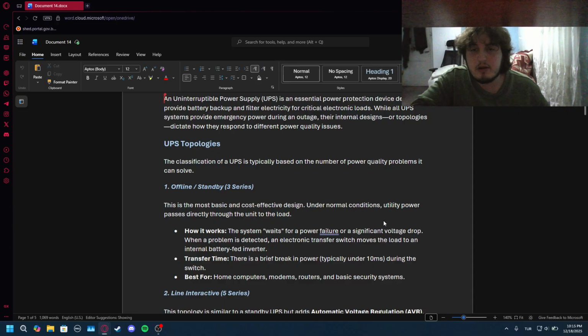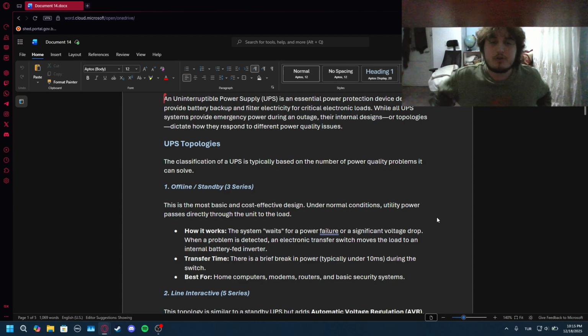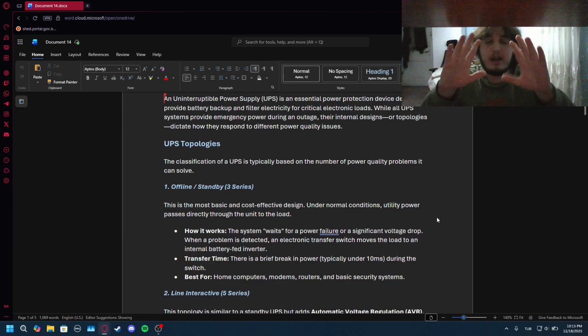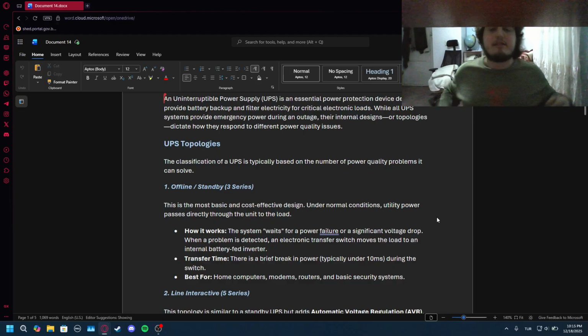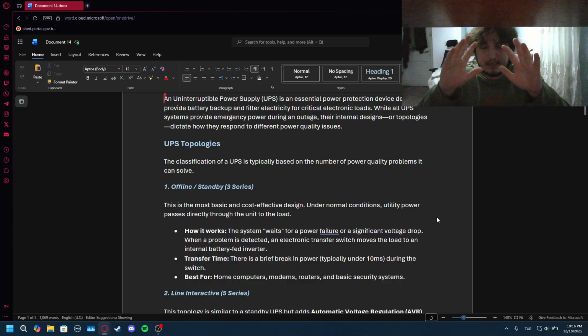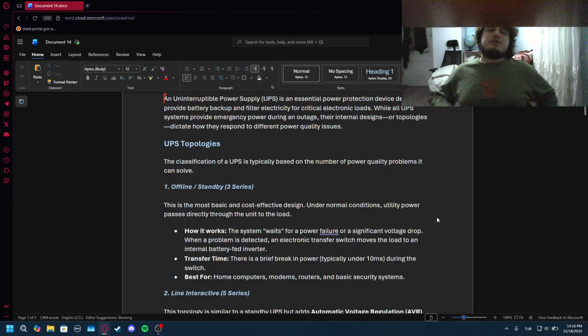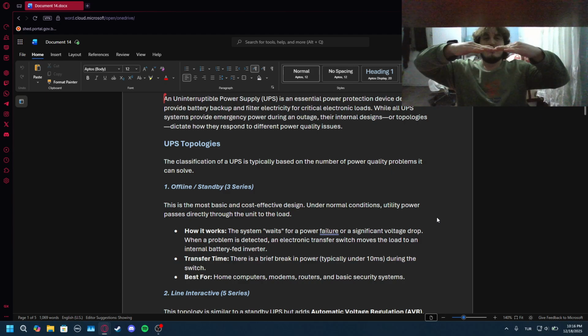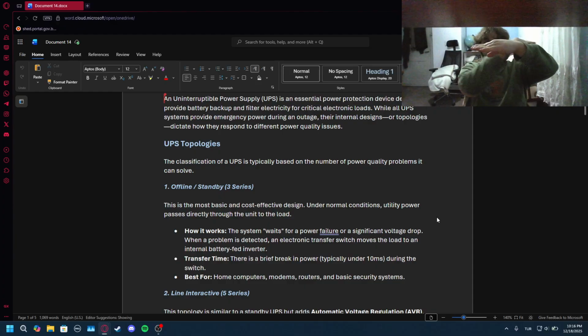Under normal condition, utility power passes directly through the unit to the load. How it works: the system waits for a power failure or a significant voltage drop. When a problem is detected, an electronic transfer switch moves the load to an internal battery-fed inverter. So basically, when you notice a power outage, or, sorry, not power, the voltage is changing really rapidly, it goes really high or really low, the system recognizes that fault. Well, not shuts down, it opens the fault case literally like this. It opens and the UPS is now feeding the entire system.